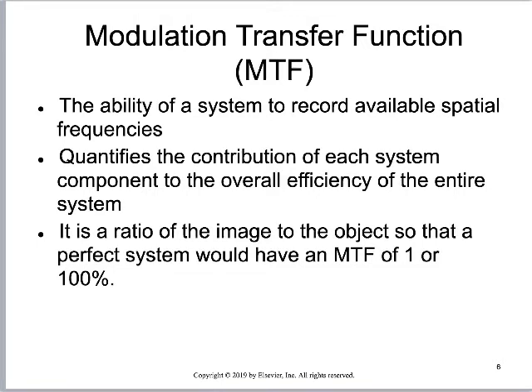Spatial frequency asks: how small are these little tiny pixels? As an aspect of whether the imaging system has good quality, the MTF is a quick and dirty way to evaluate a system — how small a thing can this system image? It's expressed as a ratio between the image and the object size. We take a very small known object, image it with the system, and measure how well the system detects it. This phantom is passed around so you can see the tiny lines.